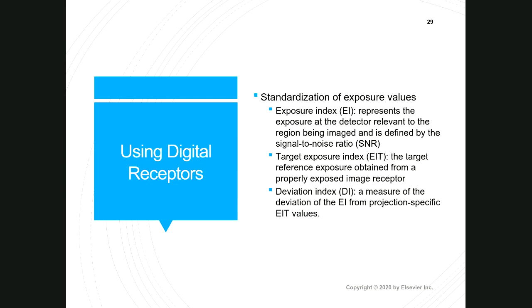Standardized, that was the word that I was looking for a few minutes ago. So there is no standardization of exposure values yet. They are working on standardizing those so that they're the same across the board, regardless of what equipment you work on. But in this particular portion where they talk about the exposure index and the target exposure index and the deviation index, these three terms are important to us because the exposure index represents the exposure at the detector relevant to the region that you're imaging, and it's defined by the signal to noise ratio.